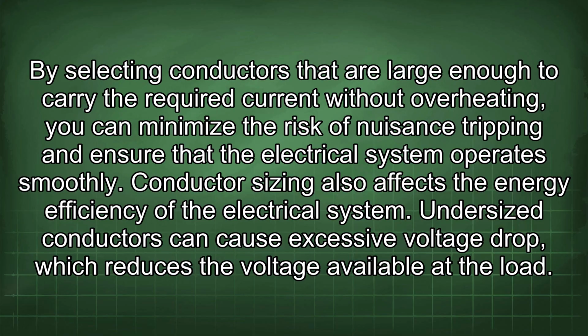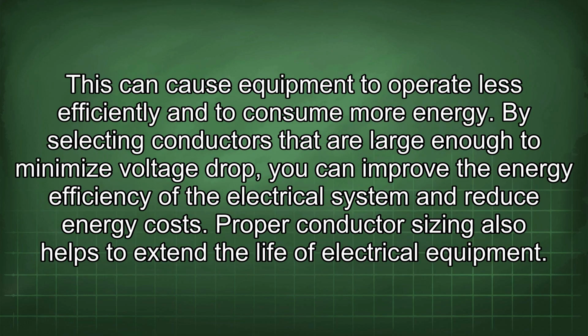Conductor sizing also affects the energy efficiency of the electrical system. Undersized conductors can cause excessive voltage drop, which reduces the voltage available at the load. This can cause equipment to operate less efficiently and to consume more energy. By selecting conductors that are large enough to minimize voltage drop, you can improve the energy efficiency of the electrical system and reduce energy costs.